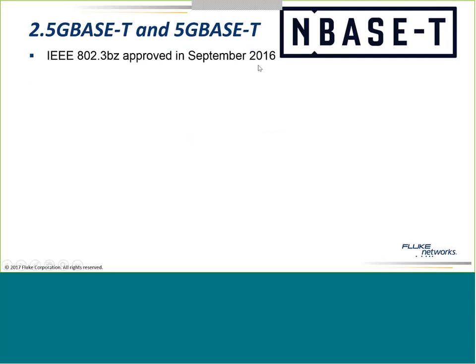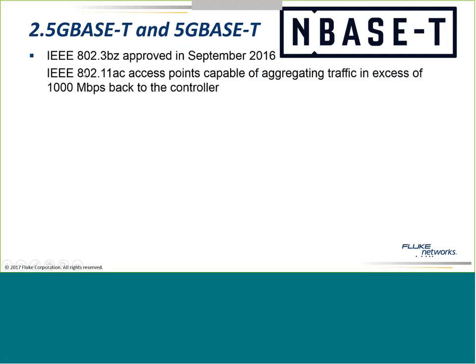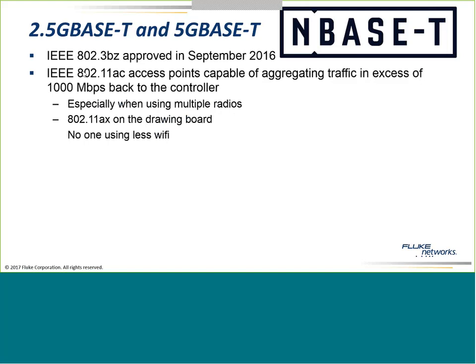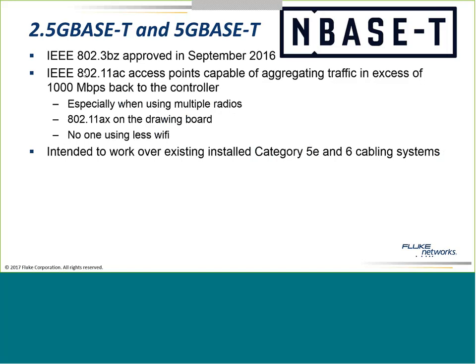Last year, 802.3bz was approved — sometimes referred to as NBase-T. What this allows us to do: we're using more Wi-Fi so that's become the bottleneck, so we want to run 2.5 and 5 gigabits over regular Category 5e and Category 6 cable. Running 5 gig will go up close to 250 MHz. We didn't actually test 5e cabling out to 250 MHz, so there's a standard — the TSB-5021 — with limits going out to higher frequencies so you can be assured your cabling will work.